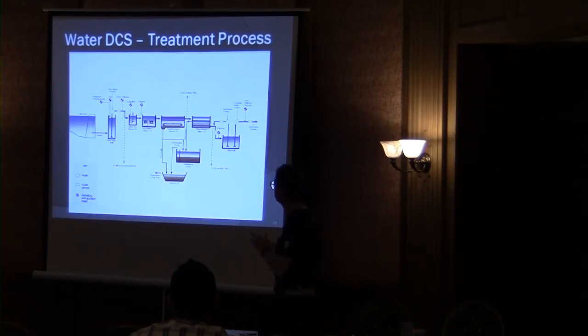And usually before 10 years ago, we used to add chlorine at the beginning because that helped actually clean out the water and oxidize contaminants. But the EPA came out with a new regulation because they determined that it caused a potential carcinogen called trihalomethanes if you had too much chlorine in the water. So we had to move the process to redesigning the clear well, which is the last step of the process where the water sits until you pump it out to the water system, to the distribution system. And we just add the chlorine at the end.